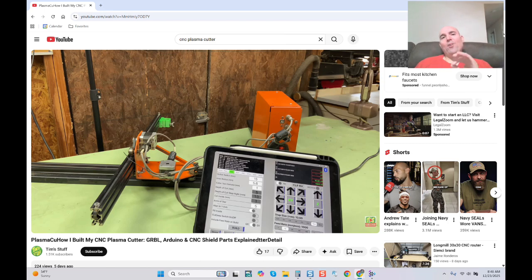This is what I ask anyone who has had problems with EMI. EMI will show its face whenever it decides to. Now, the problem is once that's built into a machine, you don't know when it's going to show its face again if you do not start at the ground level and go through and mitigate all possibilities of EMI by using best practice. Double shielded cables, proper grounding, no coatings, going through a metal enclosure, no coatings on the enclosure.